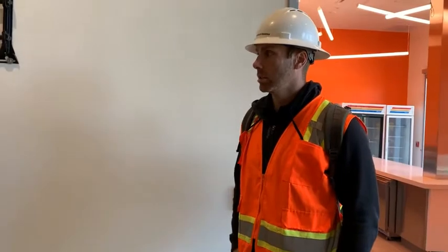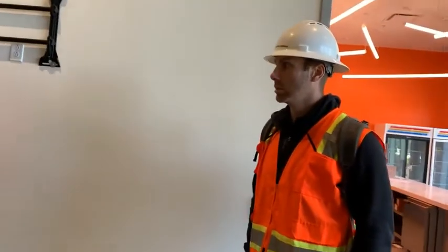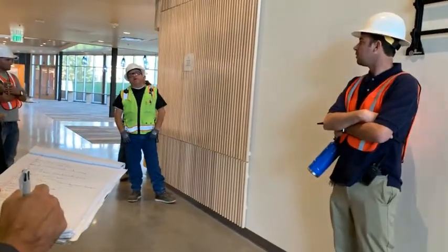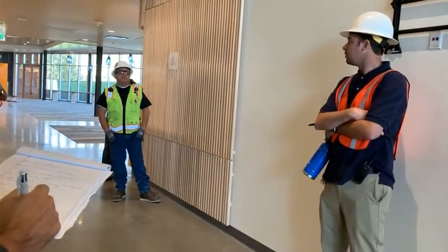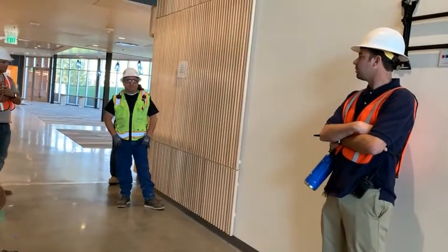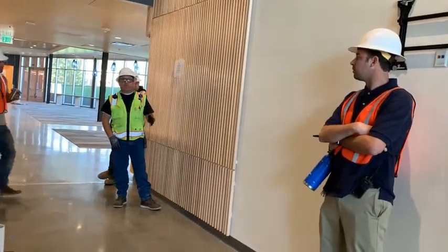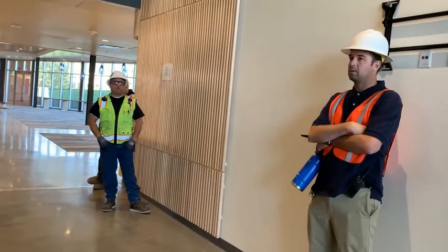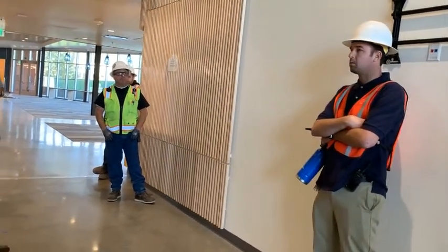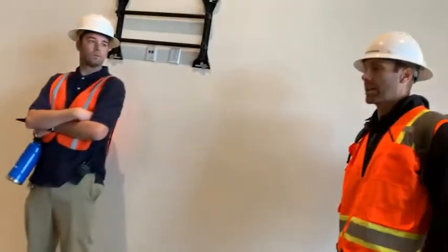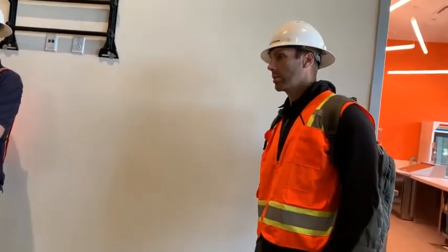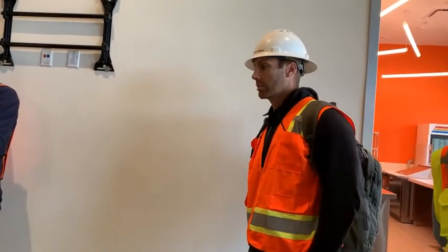One thing they programmed in was the kitchen in the back, the lights are only off from 1 till 5 a.m. And they can manually override, but they go out from 1 to 5 because I guess it's going to close at 12, so they figure it'll be done by 1 o'clock. They open at 6 and they figure they'll be in at 5. And once again, if they ever get in earlier, they can turn them on. Any of our time schedules have a 2-hour override.